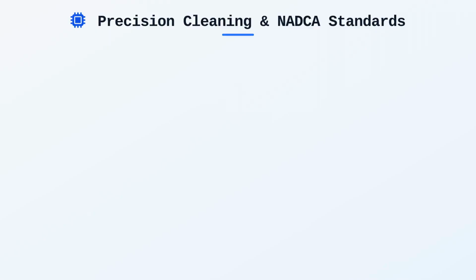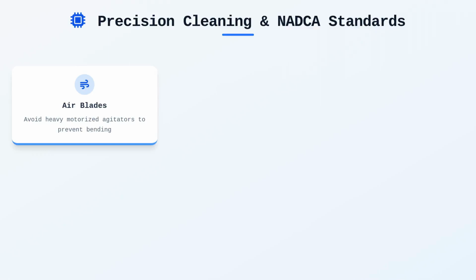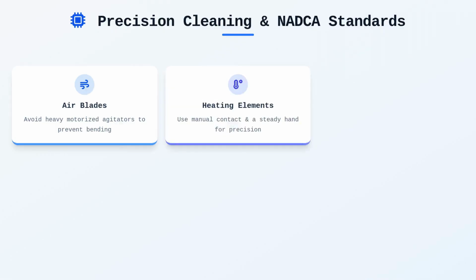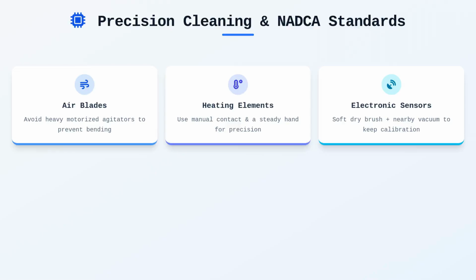Beyond the main duct runs, you will frequently encounter specialized components like sensitive sensors, air-moving blades, or heating elements that require a different level of precision. When cleaning around these objects, resist the urge to rely on heavy-duty motorized agitators. Instead, utilize manual contact methods combined with a light, steady hand to avoid bending or displacing delicate electrical connections. For electronic sensors, a soft dry brush paired with a vacuum hose positioned nearby is usually sufficient to remove surface dust without risking the calibration of the device.